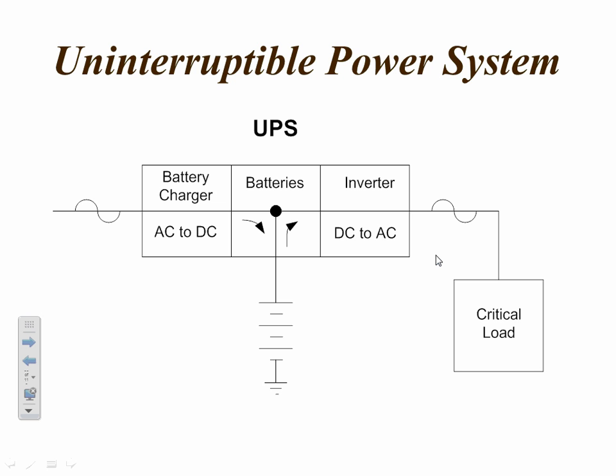Basically, they operate with three basic pieces. Very simple to explain this way. First part is a battery charger. You notice the AC wave coming in. Any battery charger is going to take AC and rectify it to DC to charge batteries, shown here in this part of it. Second part is the batteries themselves. The third part is an inverter. Okay, the inverter is connected to the batteries, and its job is to change DC back to AC. So now we've got an AC out of this device, and that in turn is powering our critical load.